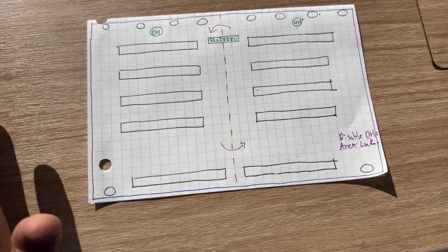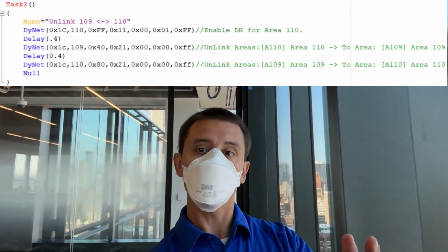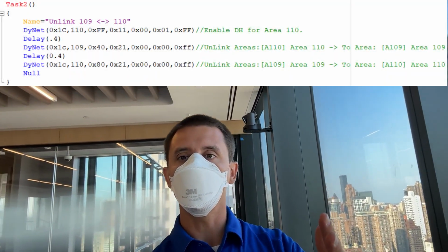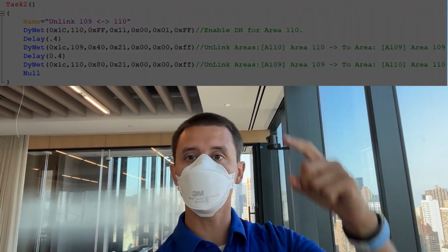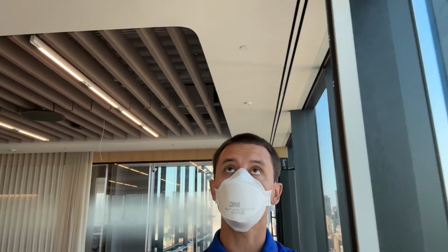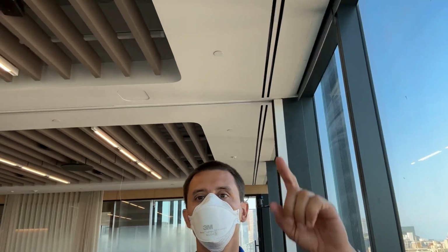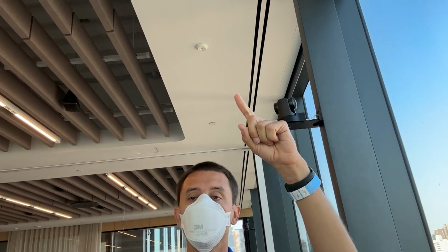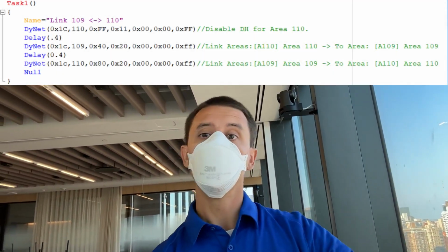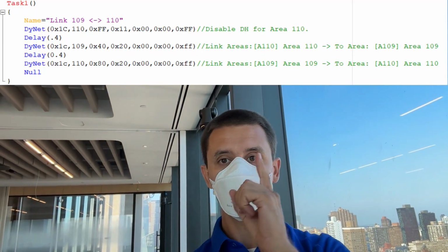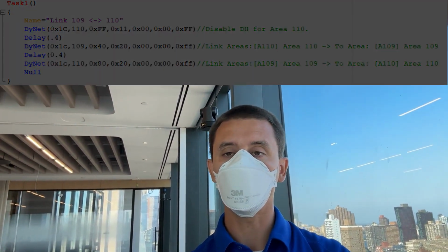And it works great. Now, in order to get this daylight harvesting zone to work together and the sensors not conflict, I have this sensor enabled to daylight harvest the row next to the window, and this sensor right here disabled so that there's no conflicts. When the partition gets closed again, I re-enable this sensor so both sides work independent from one another once again.